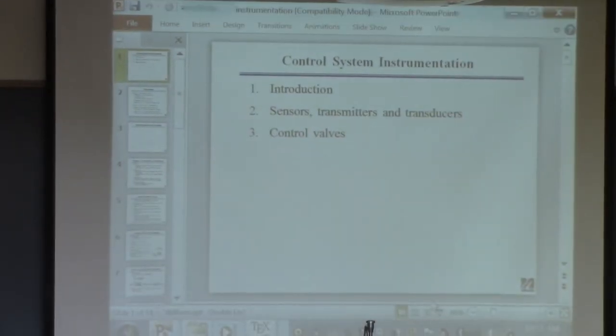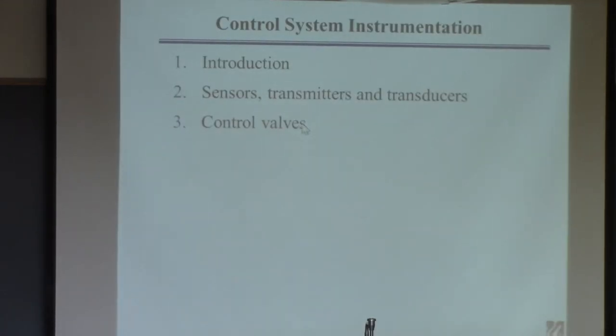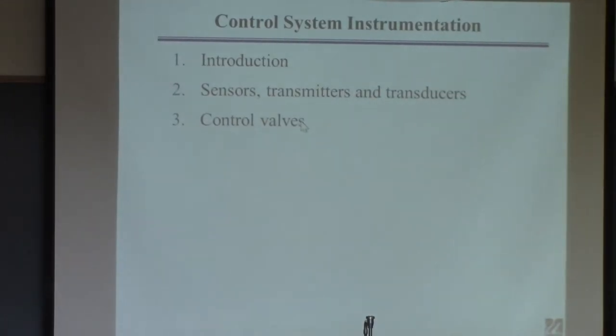When the input does this. Slam the valve closed. Slam the valve shut, and then finish the job. This will not be acceptable, you understand? Even though the output looks good, this will wear out the valve. And it's disconcerting to operations people that you're slamming valves open and closed. So this controller is tuned too aggressively. Even though the output looks great, the input is not good. So it's some kind of compromise, we'll talk about that.